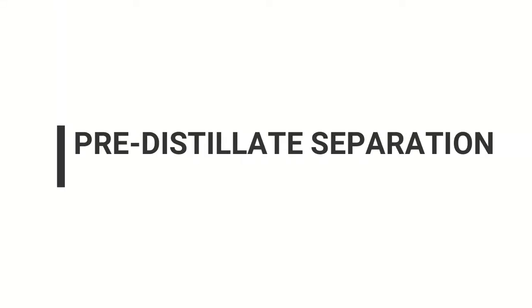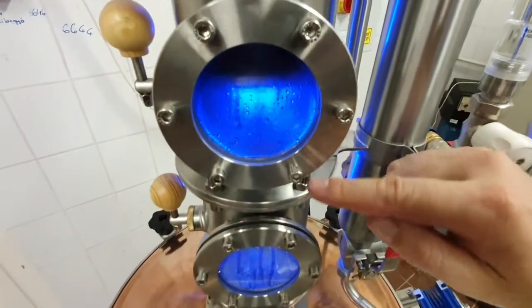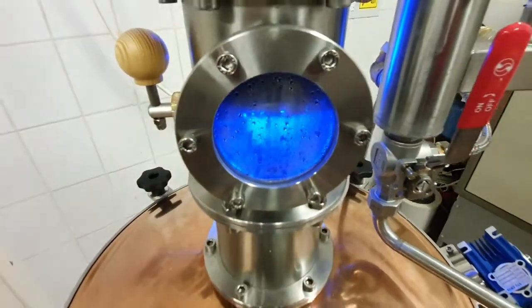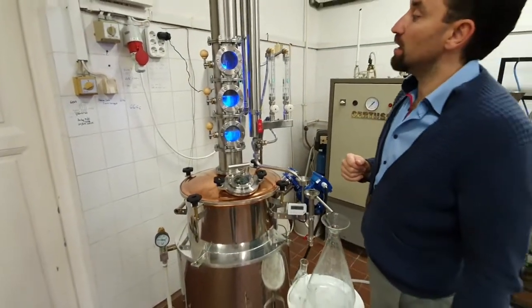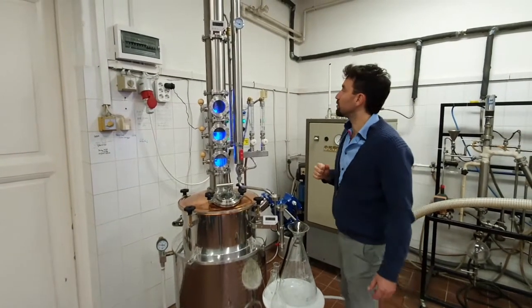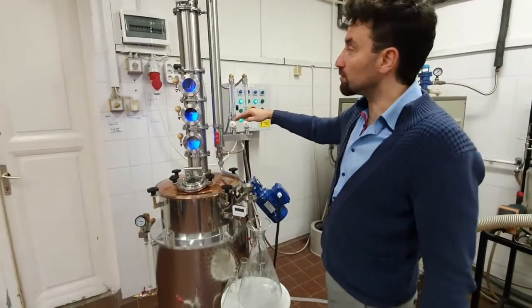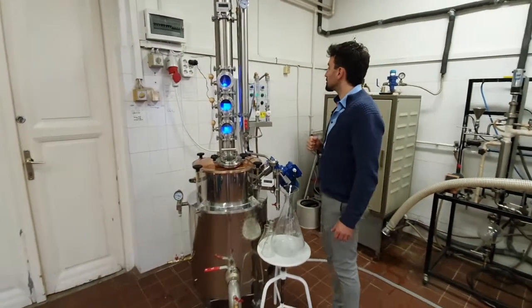Pre-distillate separation. At this moment we are heating the mash with 4 kilowatts. More accurate heating can be added with the 0 to 2 kilowatt potmeter. We will reduce the dephlegmator's flow rate from the maximum to 30 to 40 liters per hour. The head temperature will rise after this and we should keep it around 83 degrees Celsius, never going over 85 degrees Celsius during the whole distillation. What is important is that we keep the balance of the column with the right amount of heating and cooling.